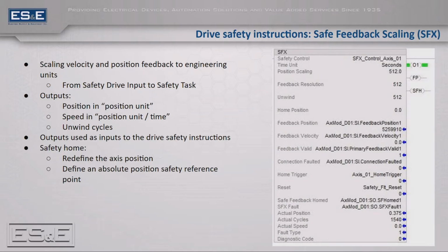So the data coming from your drives and motors, things like position and speed, has to come through one of these safety scaling function blocks in order to be used in the safety functions that we'll look at in a minute. I think Paul will look at the configuration of this in a little bit with the demonstration, but just note and highlight that you need to make sure you're using this safe scaling function block.